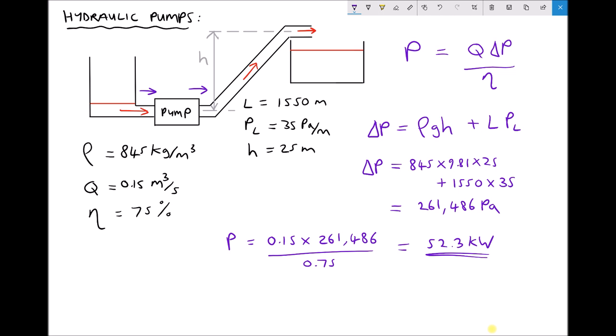So in order to overcome our pressure losses and to elevate the fluid through a height of 25 meters, our pump is consuming 52.3 kilowatts of power. As mentioned, this is the worst case scenario — if there was more fluid in the lower header tank, the fluid in the lower reservoir would assist the pump in that situation.